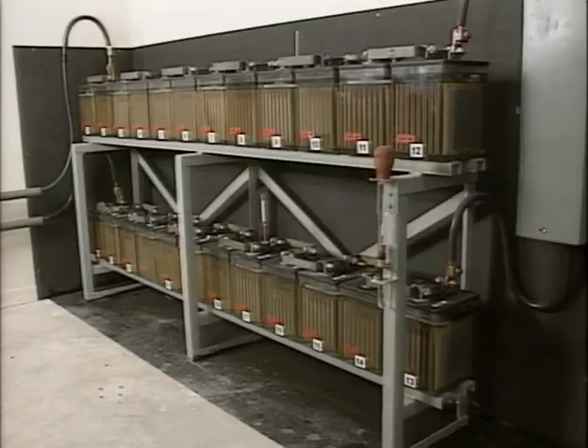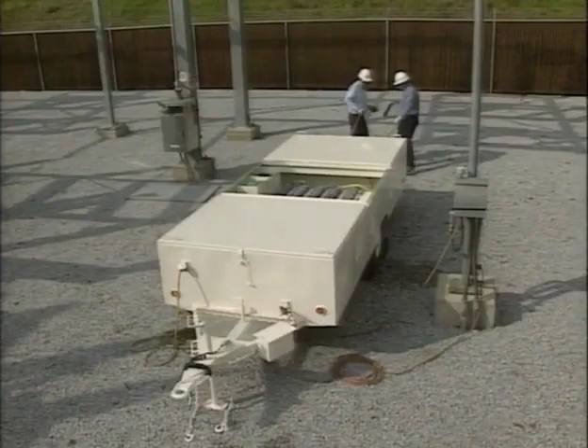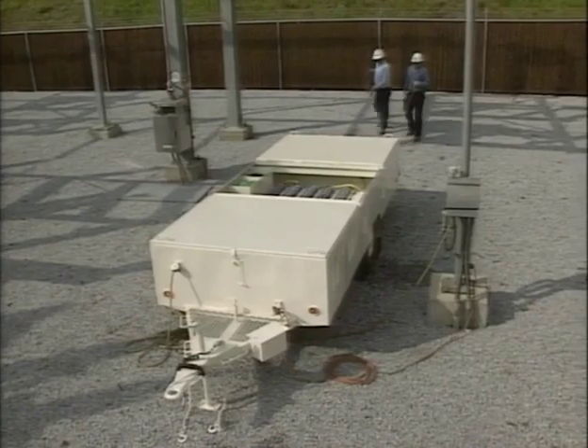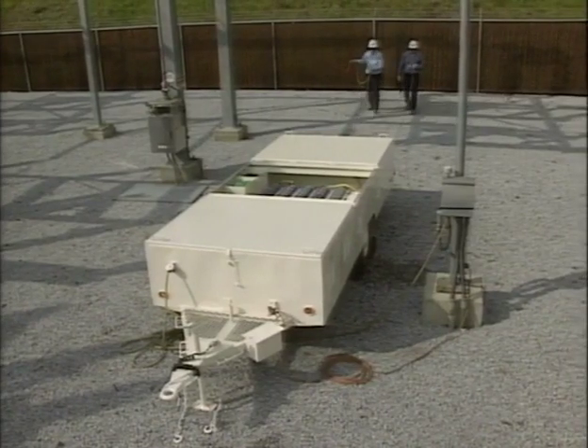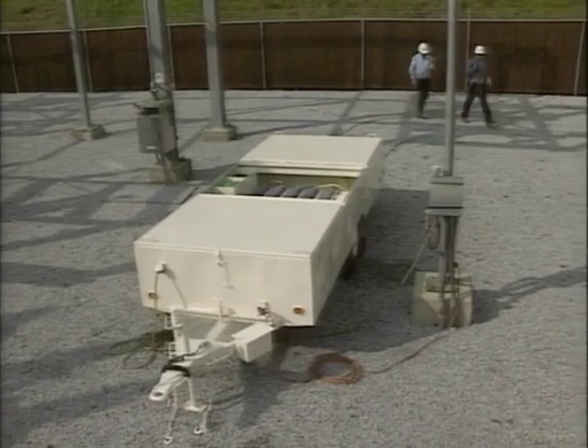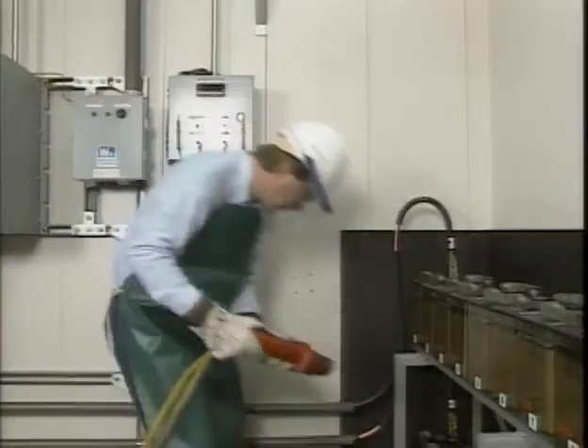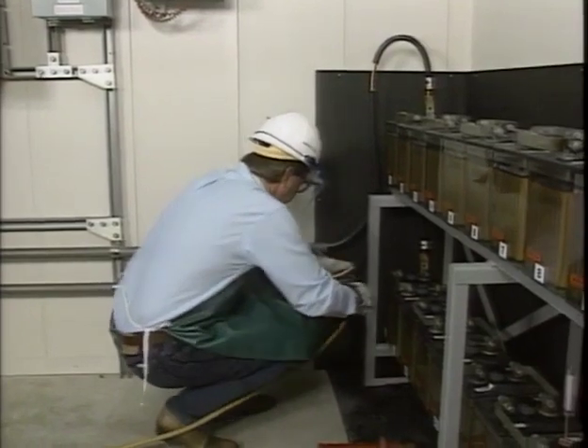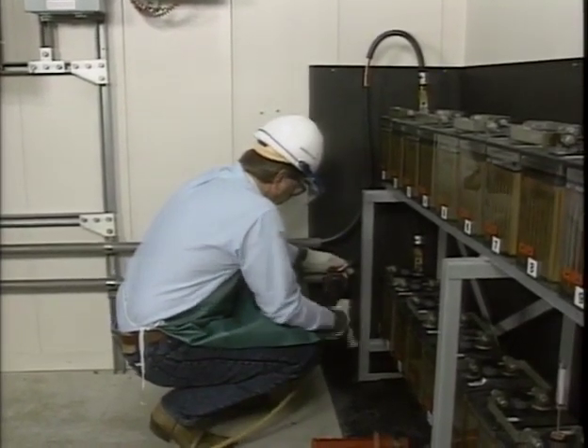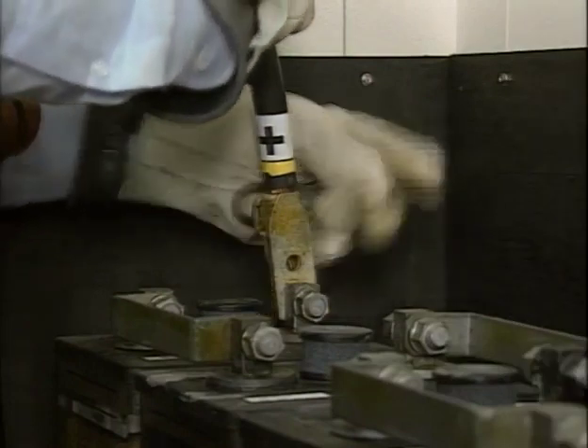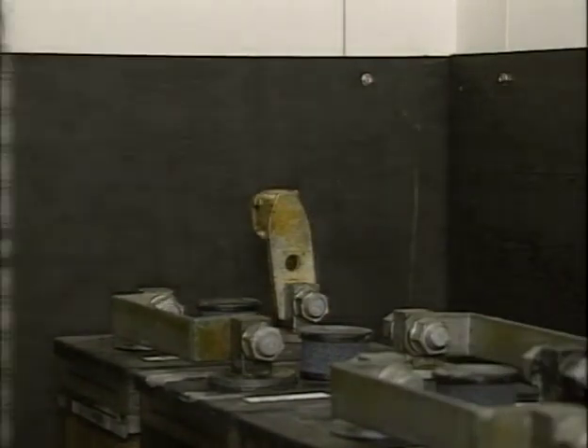In addition to the preliminary checks, the safest way to conduct an integrity and capacity test is to take the station battery out of service and replace it with an auxiliary battery. If this isn't possible, the station battery must be tested with the system load connected. For this example, a mobile battery in a specially designed battery trailer will provide the backup power for the DC system while the station battery is being tested. To replace the station battery, the mobile battery is connected in parallel with the station battery according to company procedures. Then the station battery is disconnected from the DC system.